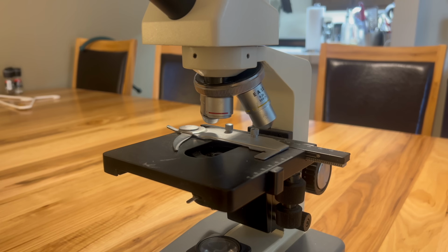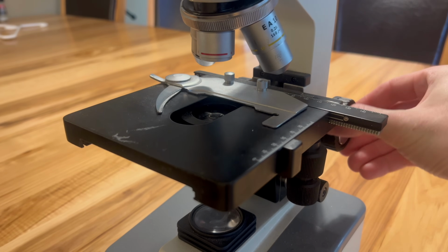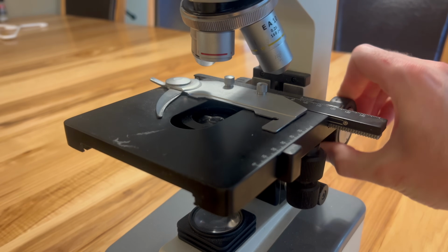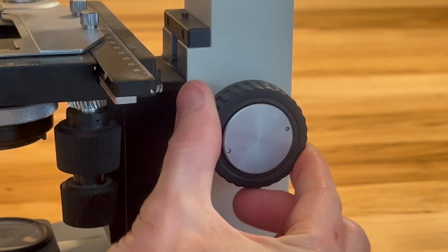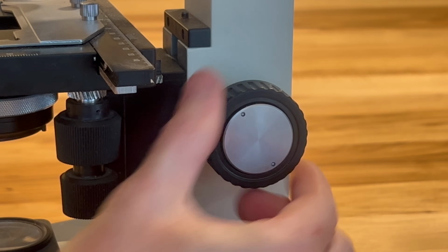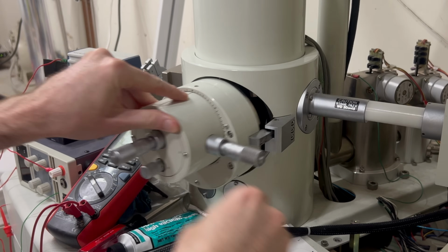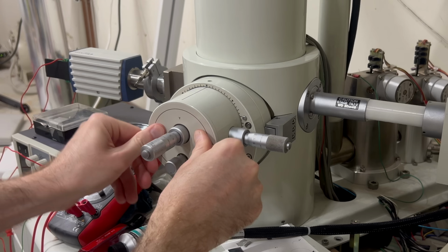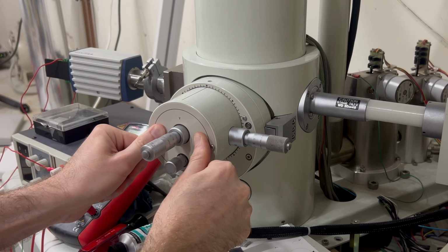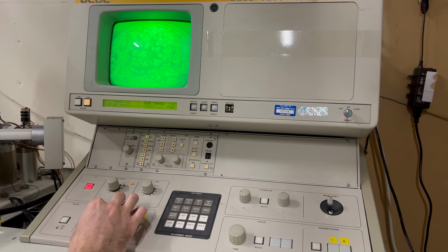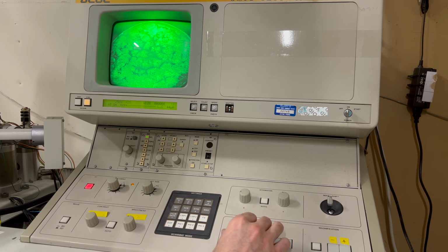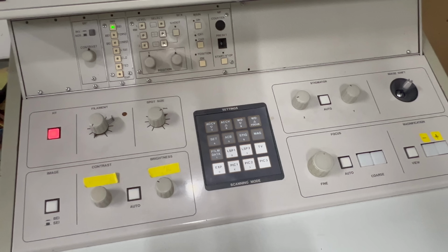Let's talk about that. In an optical microscope, you bring the image into focus by adjusting the distance between the objective lens and the specimen. This requires turning only one knob. By contrast, on an electron microscope, image sharpness is dependent on proper calibration of the electron beam. And unfortunately, calibrating the electron beam is a complicated process, requiring many different adjustments. You can see on the control panel how many different knobs there are to adjust the electron beam.